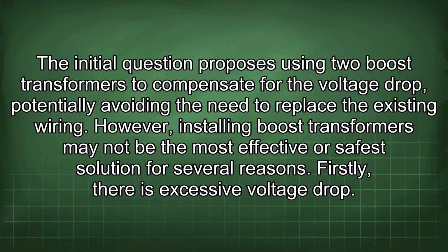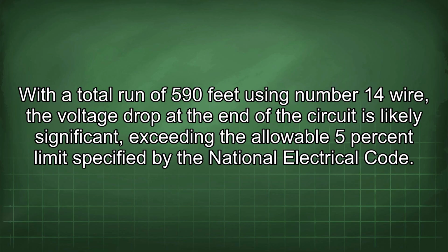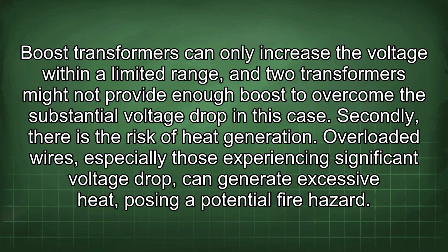Firstly, there is excessive voltage drop. With a total run of 590 feet using number 14 wire, the voltage drop at the end of the circuit is likely significant, exceeding the allowable 5% limit specified by the National Electrical Code. Boost transformers can only increase the voltage within a limited range, and 2 transformers might not provide enough boost to overcome the substantial voltage drop in this case.